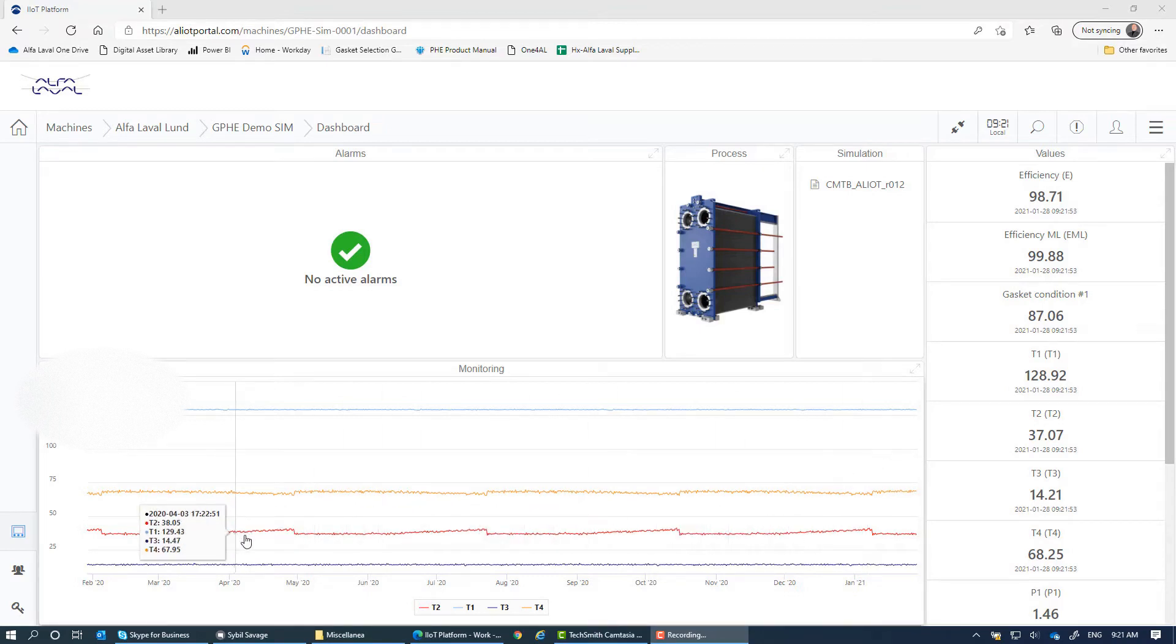What you have to pay attention to actually are those graphs that if you remember the graph that we had on the whiteboard, they are kind of the same but reversed. Because in this case you see that the pressure drop increases, increases, increases, increases. Then you run a CIP cycle and then goes down and then increases, increases, increases and you run a CIP cycle and then goes down.